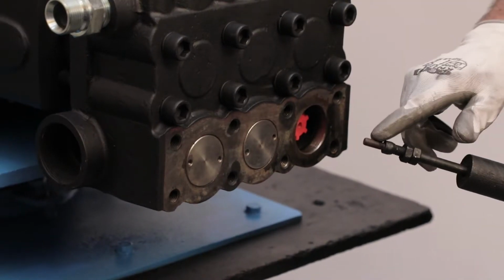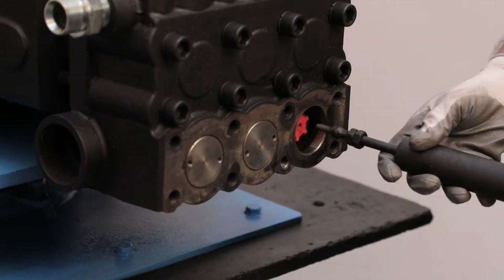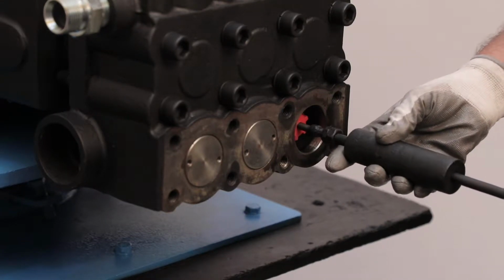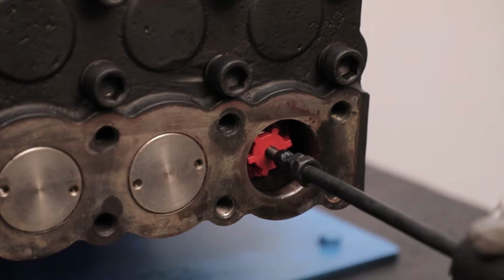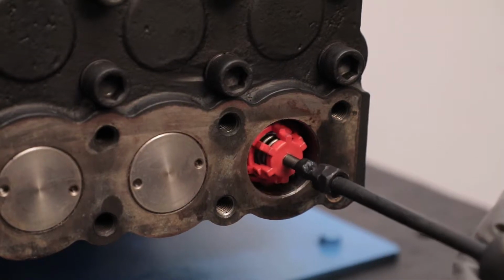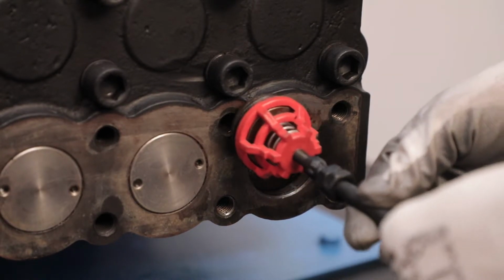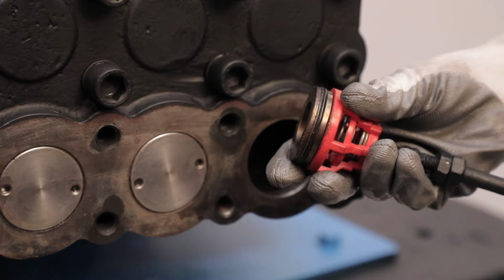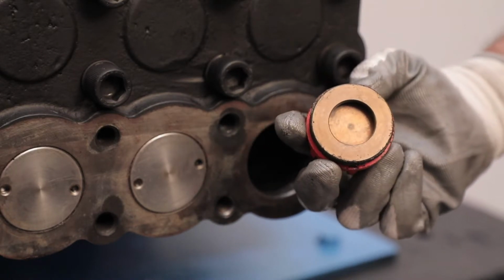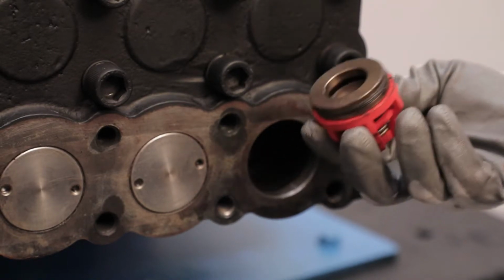Again, screw the threads of valve puller into suction and discharge valve guide and slide the weight of valve puller to pull out valve assembly. And unscrew the valve puller from it and place it on a clear surface.